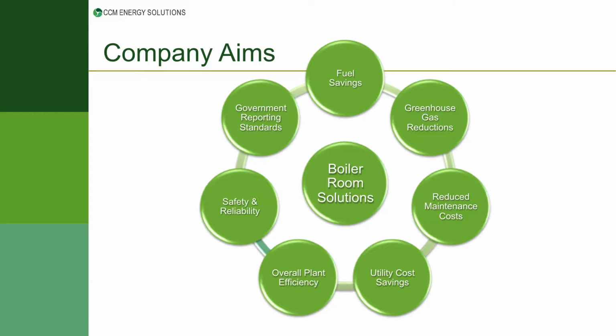So the company aims for our boiler room solutions, we're looking for fuel savings, whether it's natural gas, LPG, diesel, bunker C, whatever the fuel source that's being used through that burner, we're looking to reduce that fuel usage. From that, we also get reduced greenhouse gas emissions, reduced carbon emissions, reduced NOx, SOx emissions, depending on the fuel. We look at reduced maintenance costs. We're replacing any mechanical components. We're getting rid of all the moving parts. So we're getting better performance. There's less maintenance, less operating costs.